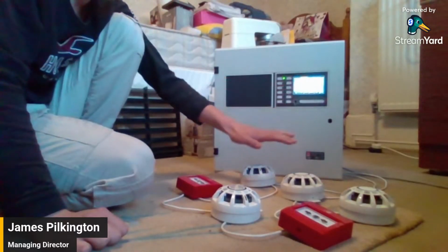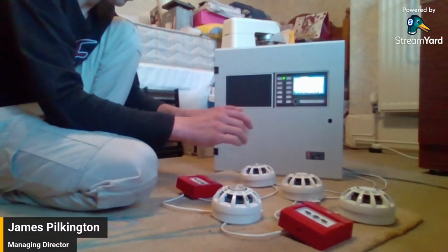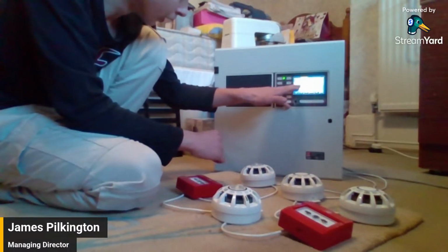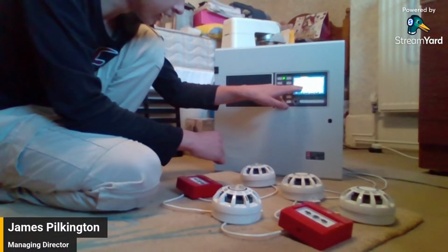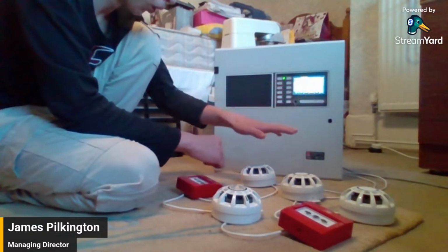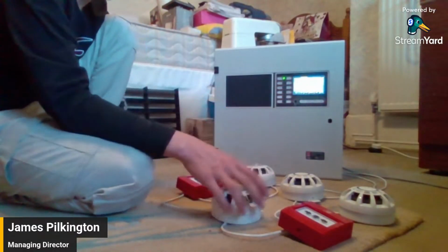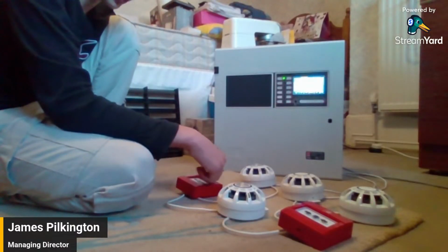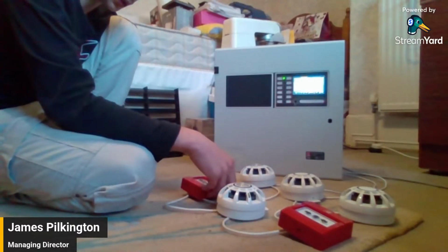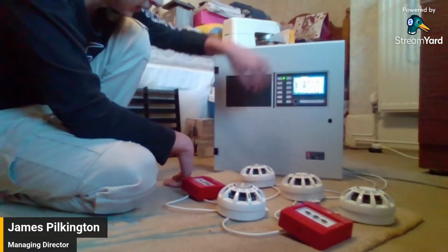So I've just connected 6 devices to the loop, so you'll get 6 faults. And these faults currently will read unlearned device. It'll tell you what the device is and what number the device is. From factory, you'll get a lot of duplicate address faults as well, because I believe these do all come pre-programmed to the same device address.